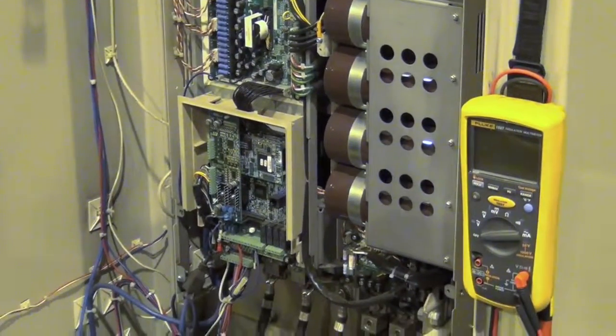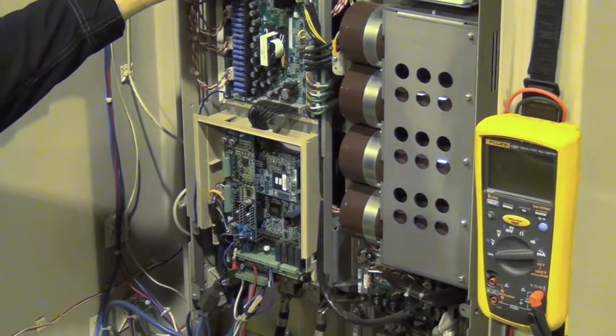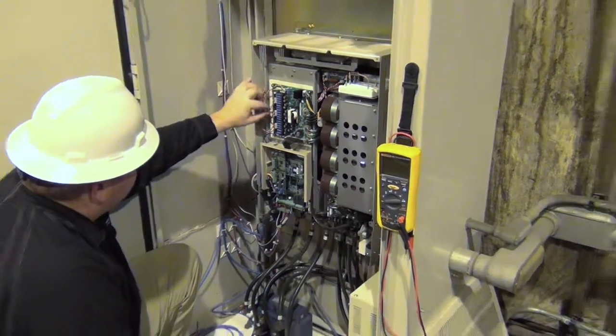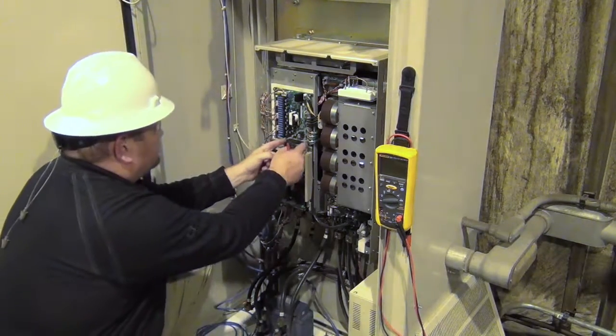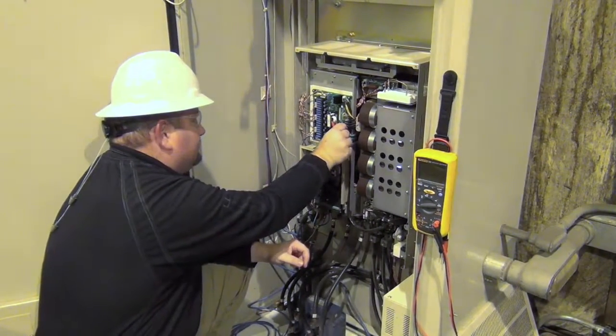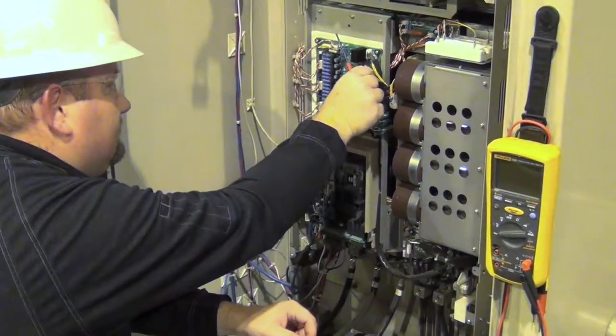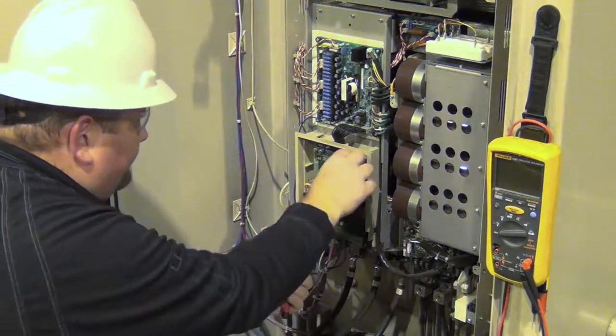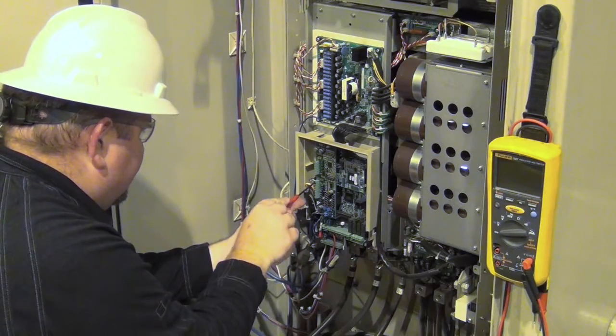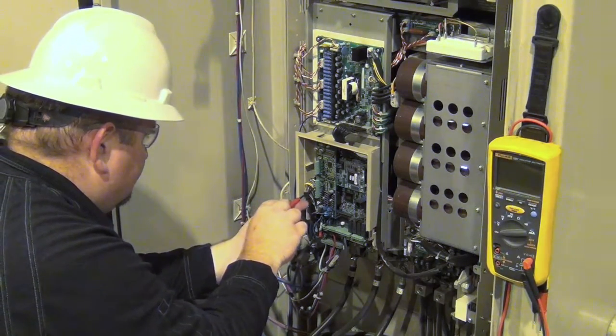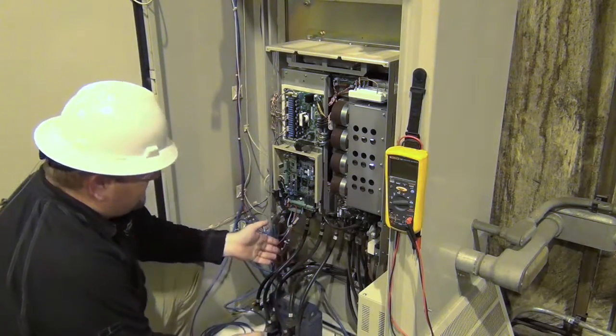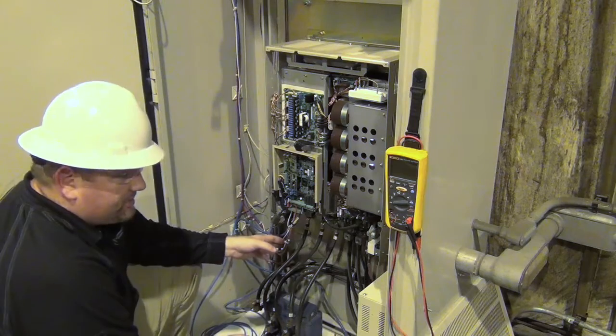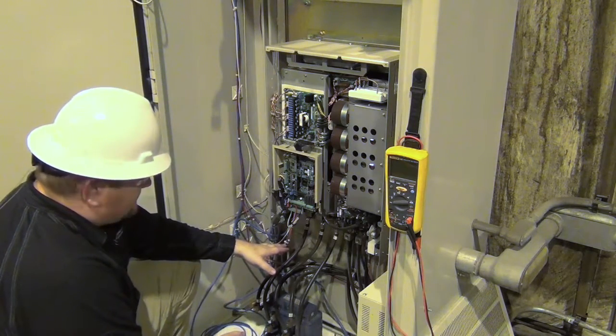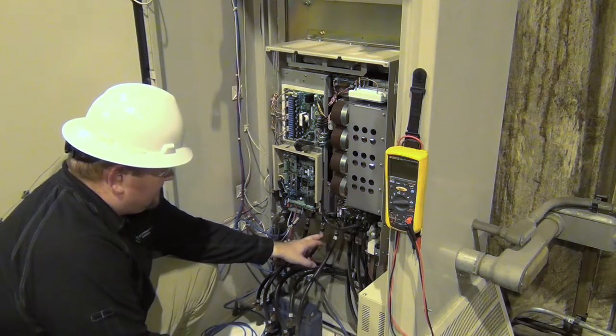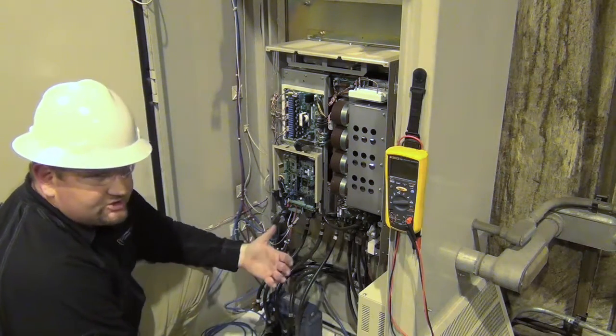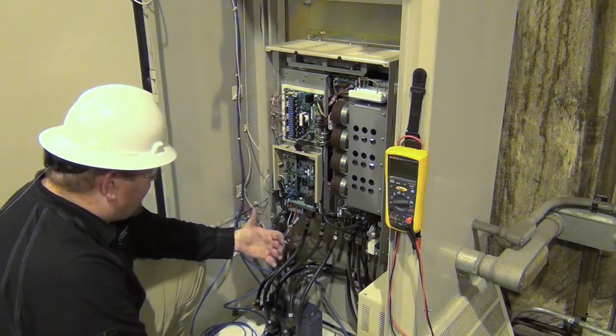So again, we're going to go through all of these connections. We're going to make sure that all of the connectors on the boards are seated well, and that all the connections are snug. So now we're going to check the main power connections. Again, usually what you want to do here is verify no looseness in the connection. While we're doing it, we're going to take a look at the terminal connector. Again, make sure there's no signs of discoloration and make sure that the wires are properly seated.